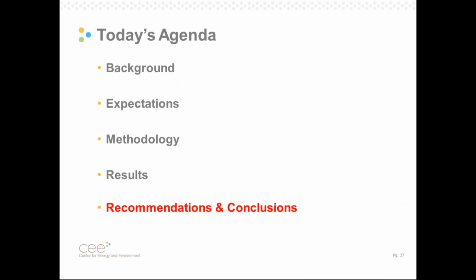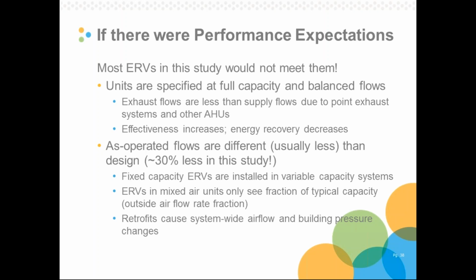All right, so I've got this mix of recommendations and conclusions. I want to really hammer on how we should use this information when we think about energy recovery in Minnesota, because a lot of the literature is frankly focused on more mild climates and gives a lot more attention to cooling and not the practical issues, especially as we find them. First thing I want to say is if there were performance expectations, if we were measuring performance with respect to design conditions, most ERVs in this study would not meet them. Units are specified at full capacity and balanced flows, but in practice, exhaust flows are less than supply flows. We have toilet exhausts. We have kitchen exhausts. We're not sending all our exhaust air back to our ERVs. In this situation, performance actually increases.